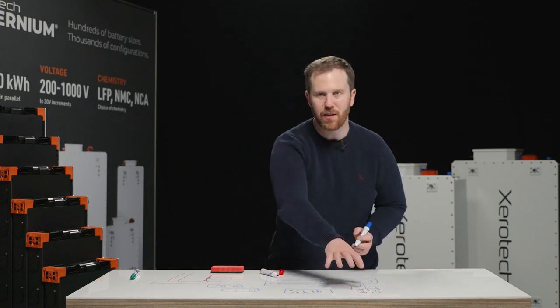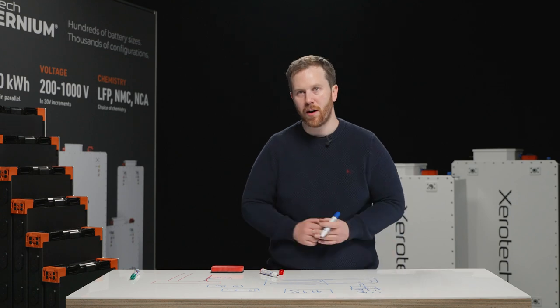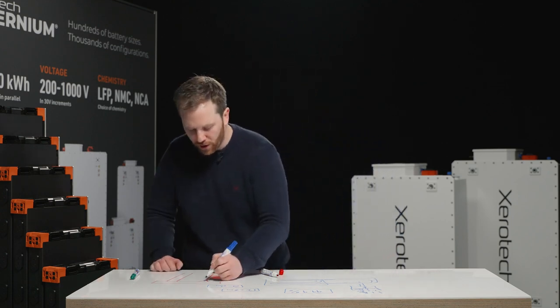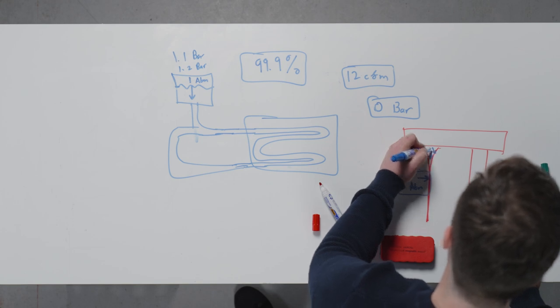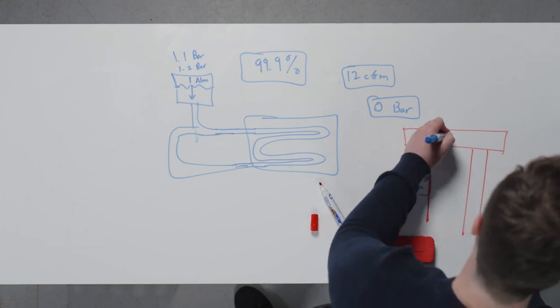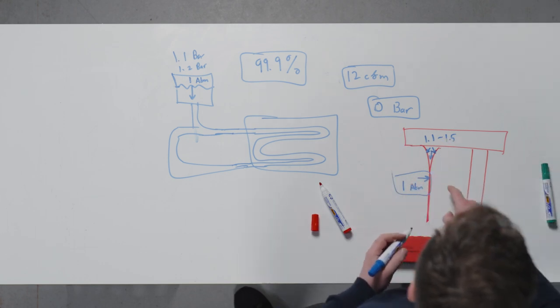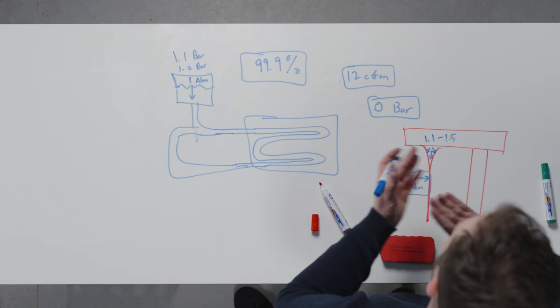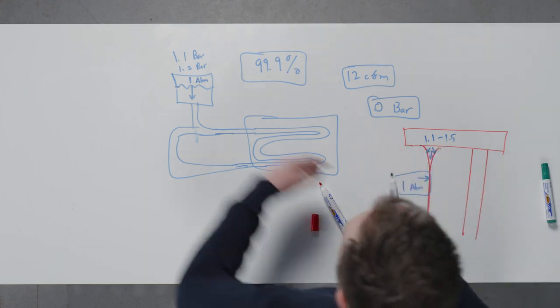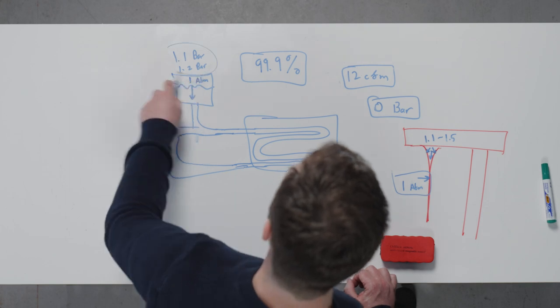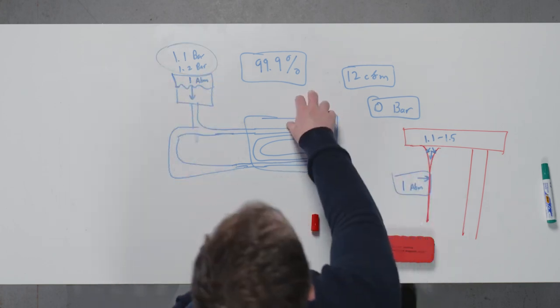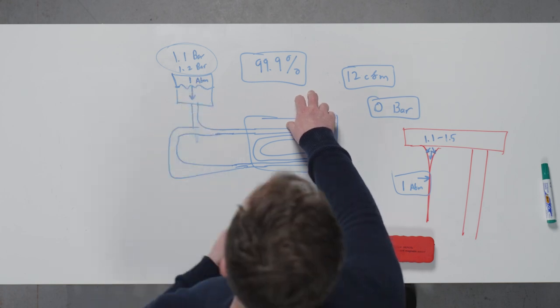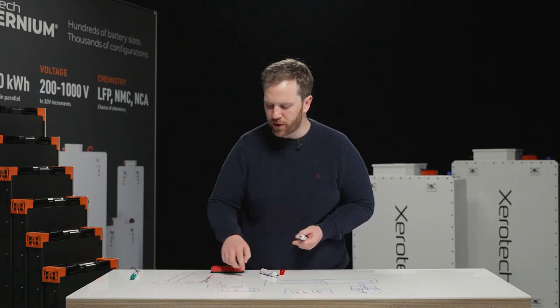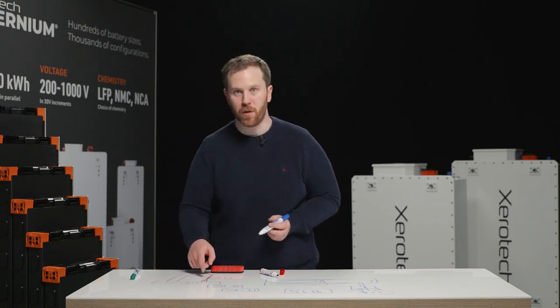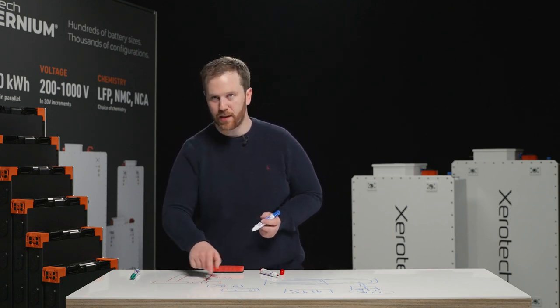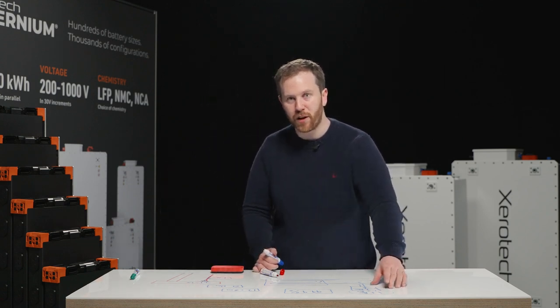With respect to ambient, a slight positive pressure of just a few hundred millibar above atmospheric pressure will result in the outward pressure here being 1.1 to 1.5. So you've got a net pressure here that basically overcomes the outside atmosphere, holding the ducts closed. So it'll open the duct and the coolant will flow through it. So this pressure here is different to the pressure we're describing in the system of a maximum of 1 bar, because we're talking here about the differential pressure. The difference here is actually only 0.1 bar, 0.5 bar, because it's the difference between inside and outside. So that's really important for filling coolant into the system.